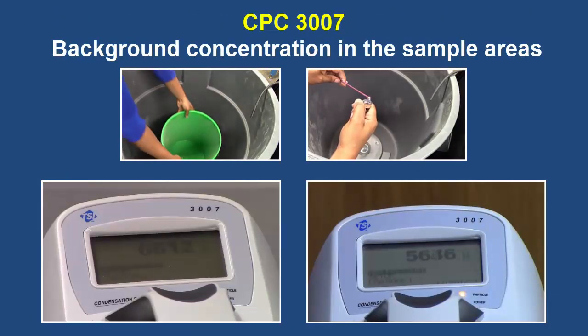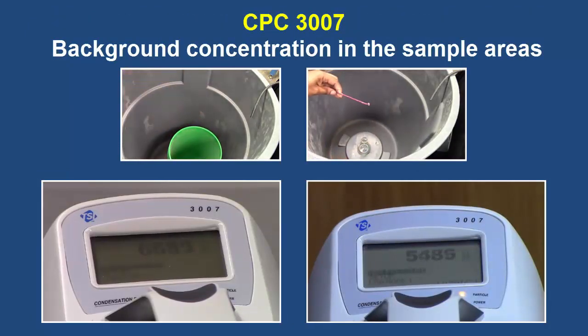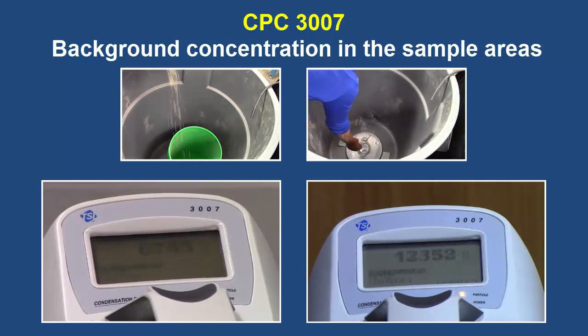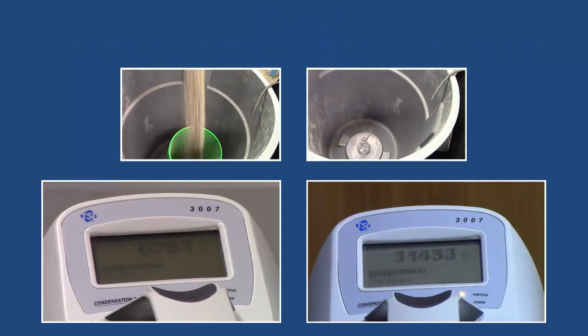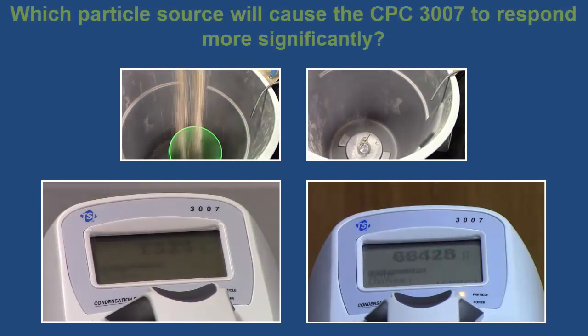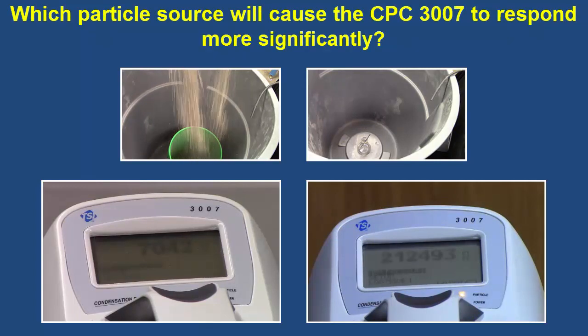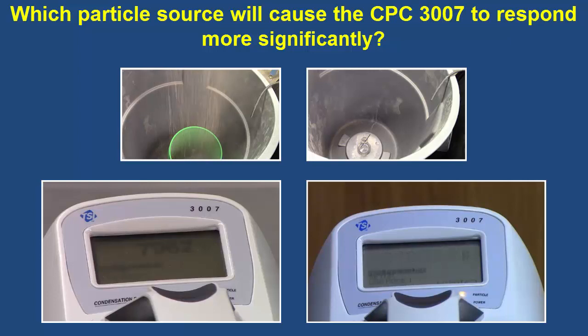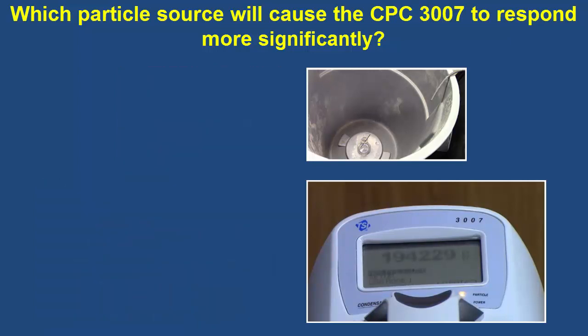The third direct reading instrument to observe is the condensation particle counter, or CPC, which measures number concentrations. Here are the background number concentrations of the two sample areas. And here are the particles generated by the cat litter and incense stick in the sample areas. There is a significant increase in number concentration from the incense stick. The CPC often reflects the presence of smaller or nanoparticles, being that these particles can be numerous in the air compared to larger ones.